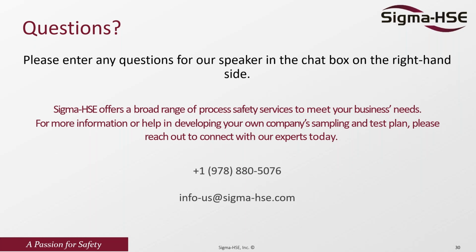Okay, excellent. Thanks, Doug. Another one is more on the written maintenance program about it being developed. The question is, what does this look like? For example, how would it go over and beyond work instructions on the equipment? Yeah, that's a good question. You should have an overall document policy that covers, in general, your equipment, your vessels, and then each vessel, interlock, pump, needs to have a separate work instruction that's tied back to that policy.